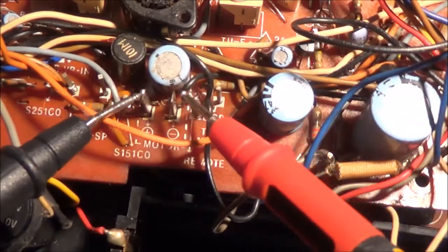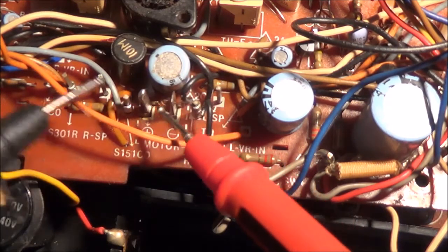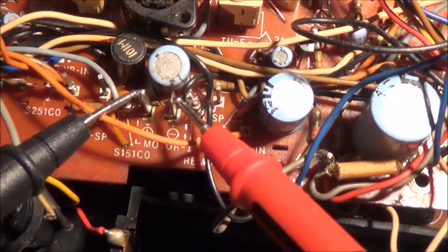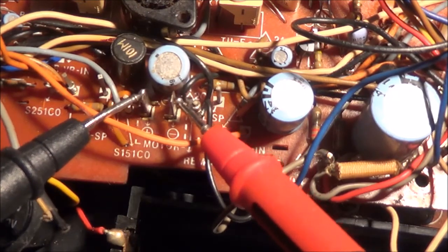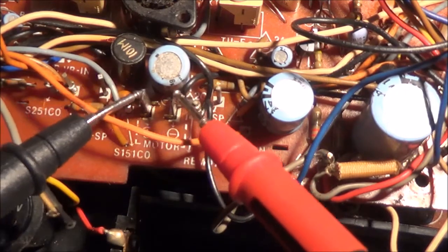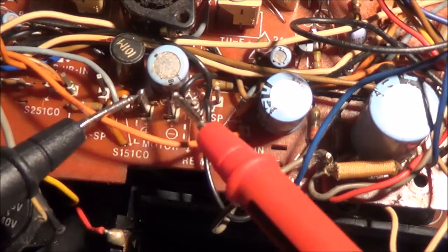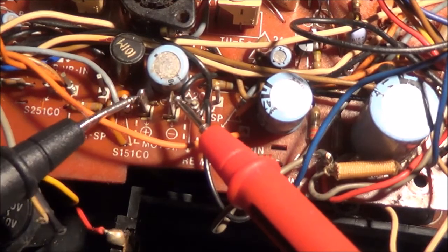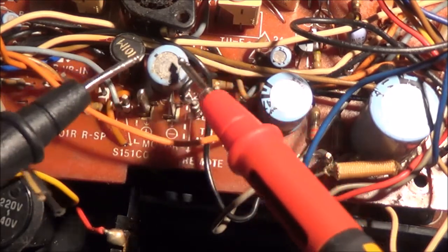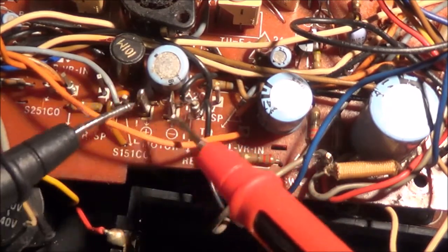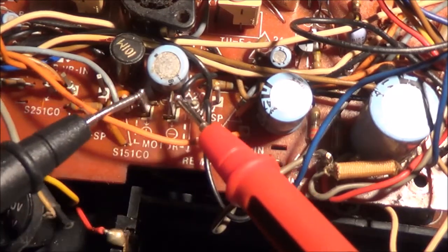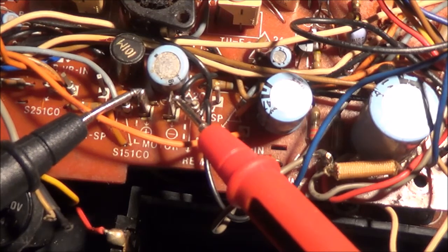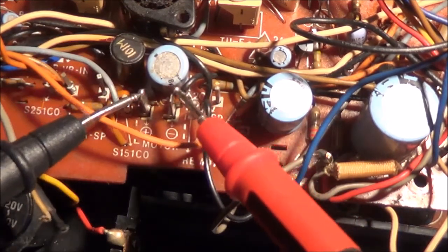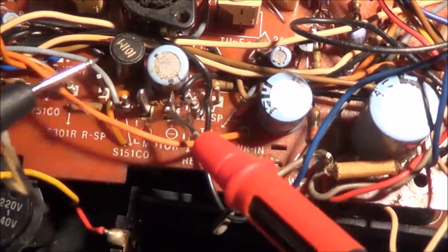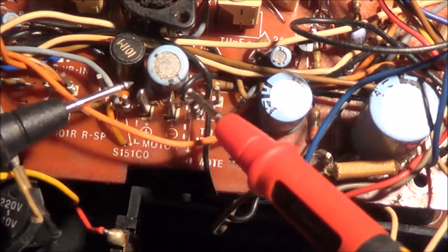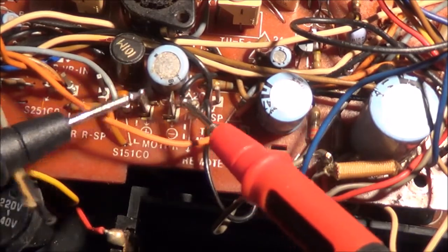Again here, if we've got full voltage here and the motor wires are still connected, we can safely assume the motor supply voltage going up to the motor is good. If we got 0 voltage, or it's really low, we could have a problem in the motor, or it could be a problem with the supply voltage — we don't know, so we'd have to disconnect this and troubleshoot. Either the problem would be before the motor, or it could be in the motor itself.